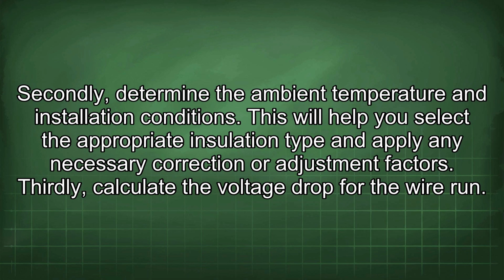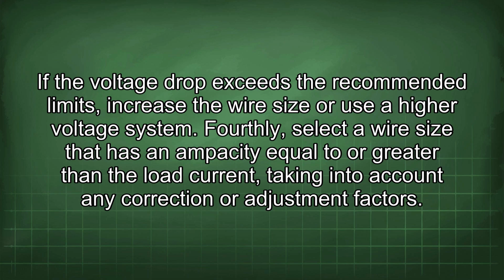This will help you select the appropriate insulation type and apply any necessary correction or adjustment factors. Thirdly, calculate the voltage drop for the wire run. If the voltage drop exceeds the recommended limits, increase the wire size or use a higher voltage system. Fourthly, select a wire size that has an ampacity equal to or greater than the load current, taking into account any correction or adjustment factors.